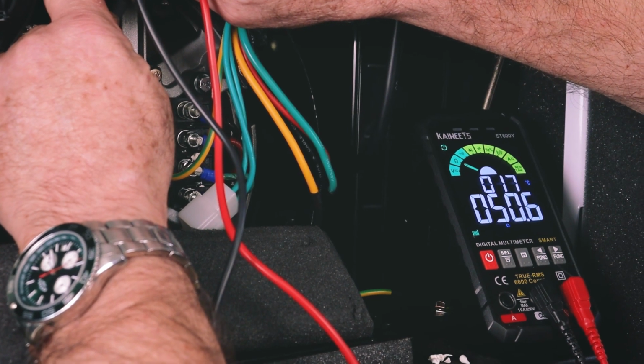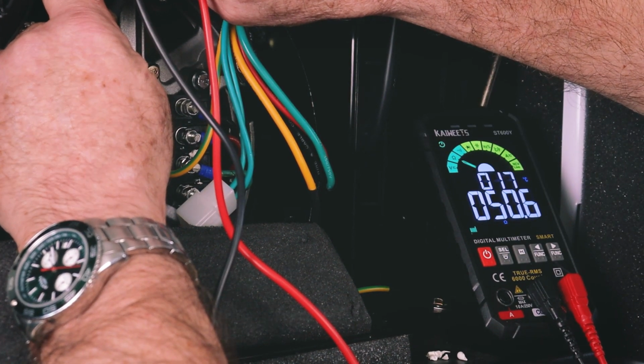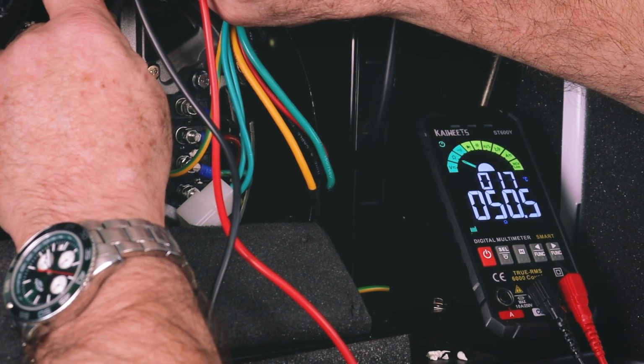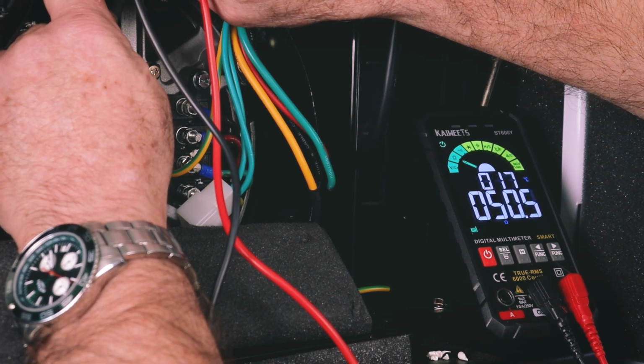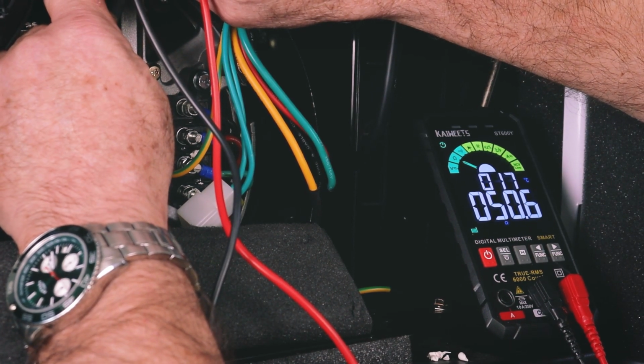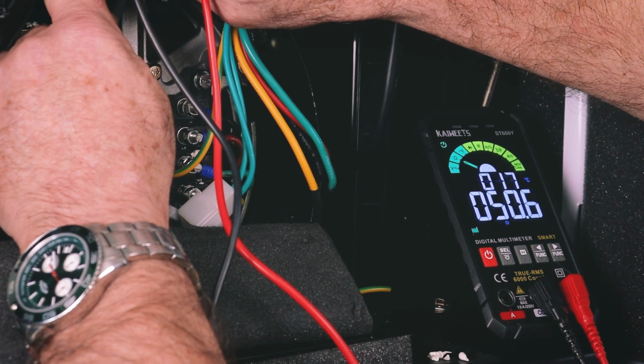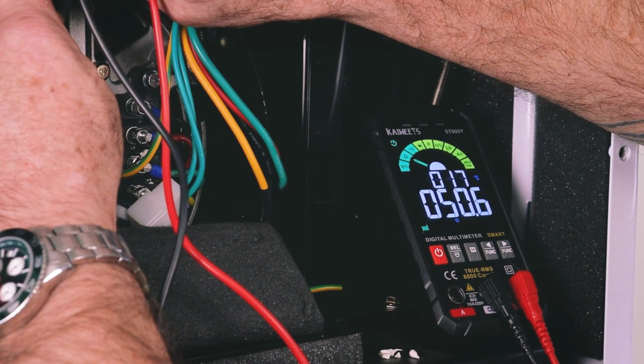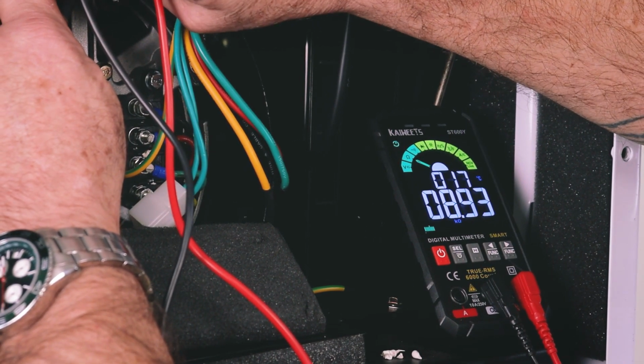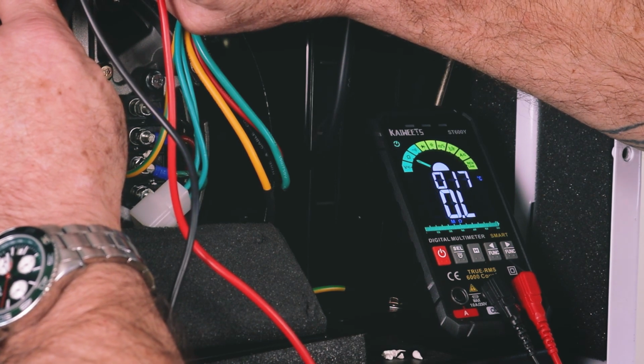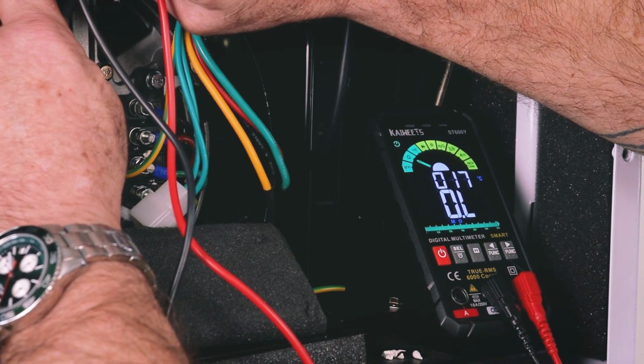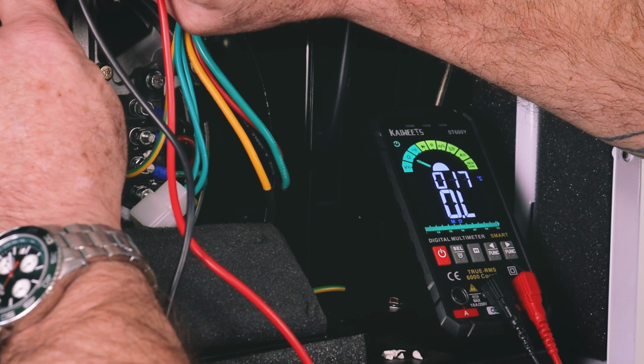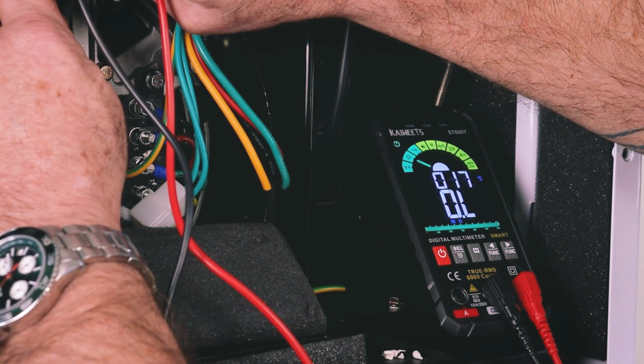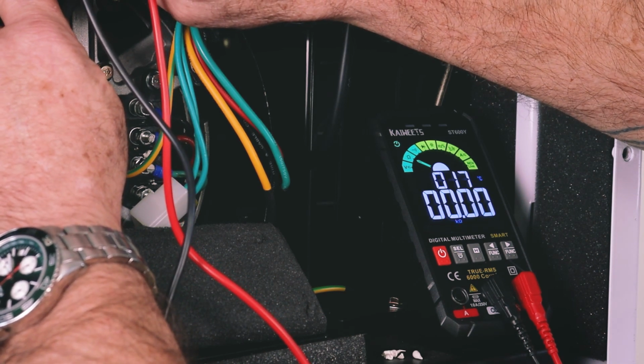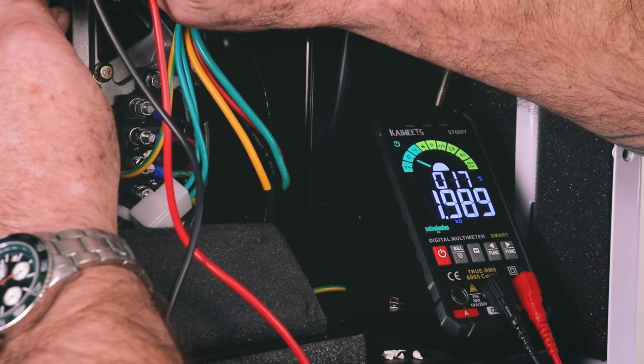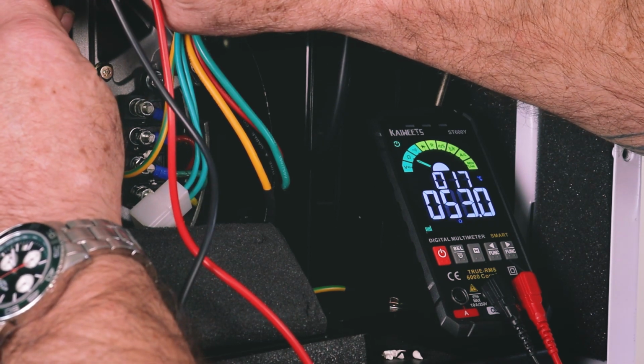So if I look at the meter, I'm on them now. I've got 50 ohms on my meter. That's around where we should be. I mean, if it's 48 to 58 ohms, something like that, that's the resistance we should be looking for. Now, if I had OL, that means that the rotor is broken down. I should get a connection through there. It's another winding. So if I was over limit, that means that rotor is broken down and we need to replace the rotor. Can I get back on it?